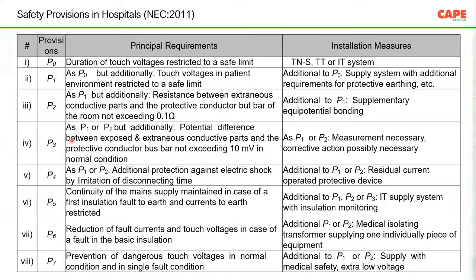I will just read P0, P1, P2, and P3. P0 means touch voltage restricted to a safe limit. This is by installation, TNS, TT, or IT system. But as I said, nowadays TT is not recommended. TNS is recommended for medical location. P1 is P0 plus touch voltage in the patient environment restricted to a safe limit. What does it mean? It means the touch voltage is lesser than 25 volt.